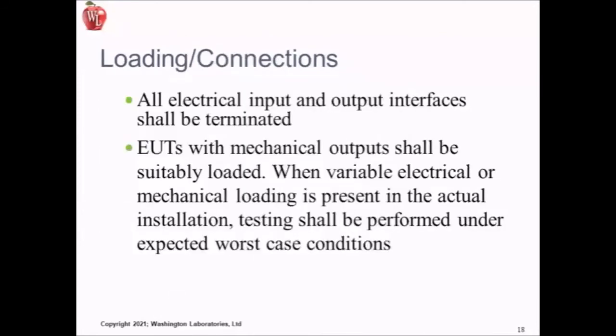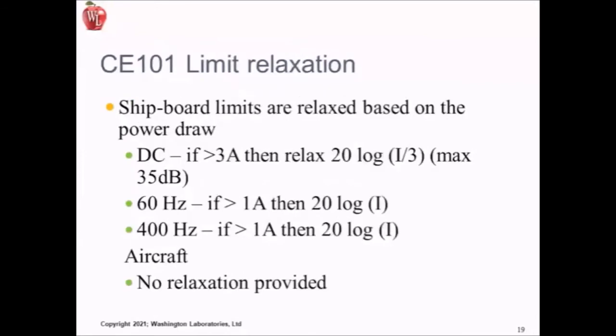Also prescribed in the G are loading and connections, and it's necessary that you terminate all electrical and output interfaces in order to simulate the actual device installation. And if you have some kind of mechanical output, maybe a motor or an actuator, you should take into account the mechanical loads as well while you're doing the evaluation. So, go into some of the tests.